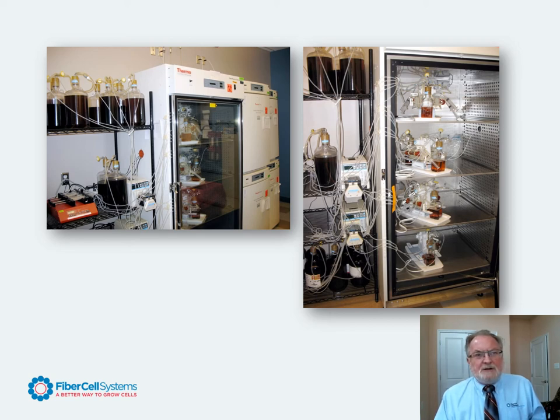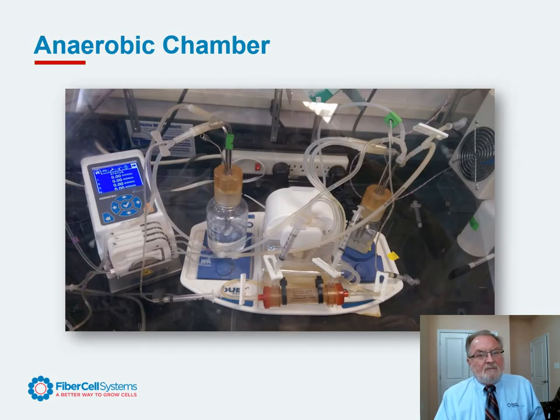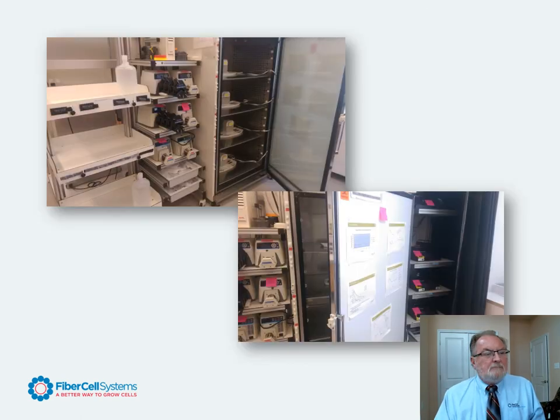Here we can see the syringe pumps for dosing. The system is also small enough that it will fit easily into an anaerobic chamber so that we can evaluate drugs against anaerobic bacteria as well. It can be easy to manipulate the system if we have dedicated carts for each of the components. Here we have a separate cart for the diluent and waste, another cart for the peristaltic pumps, and then the hollow fiber infection model system itself is inside this light tight incubator for drugs that are light sensitive.